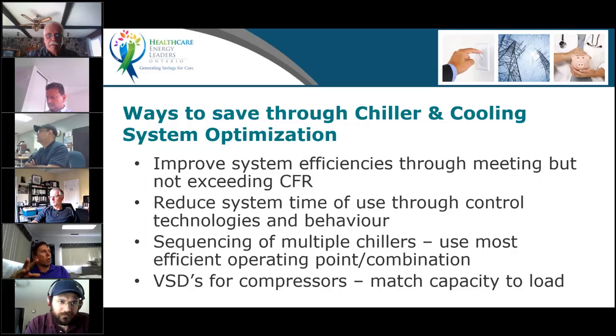If you've got multiple chillers, which is very, very likely, depending on the type of chiller, how are you going to sequence those chillers? How are they arranged? You don't just need to know I have 3 chillers. Are they 3 chillers in parallel? Are they 3 chillers in series? Are they in series counterflow, like the most efficient type of combination sometimes in larger plants? So you need to know that before you start optimizing.